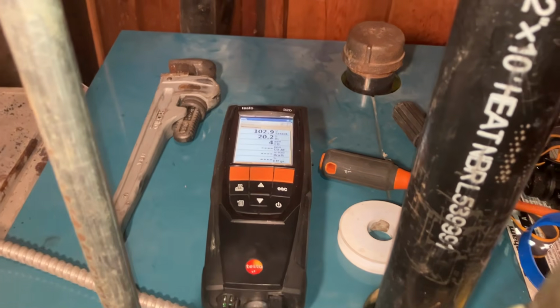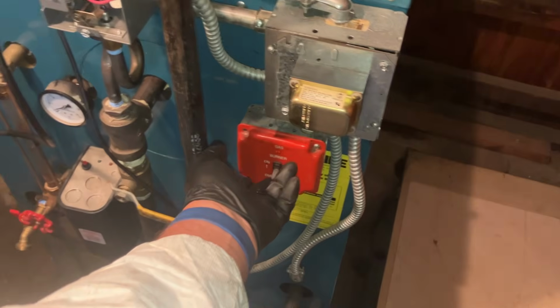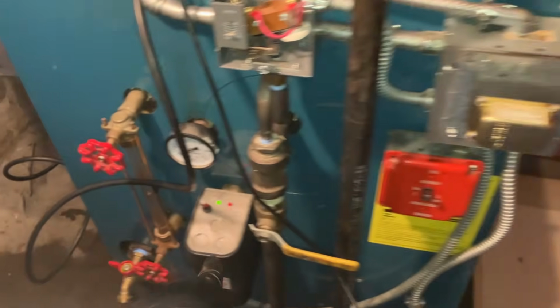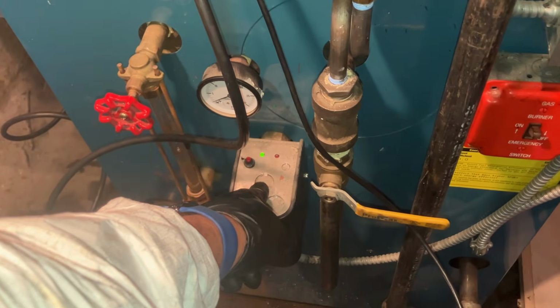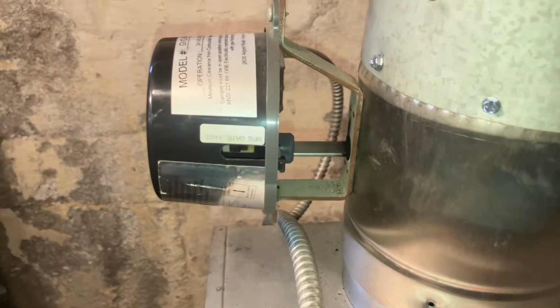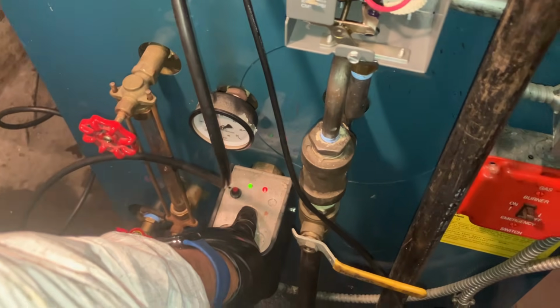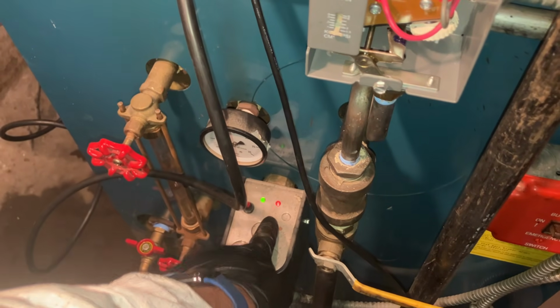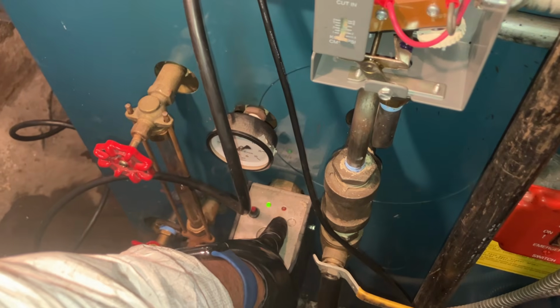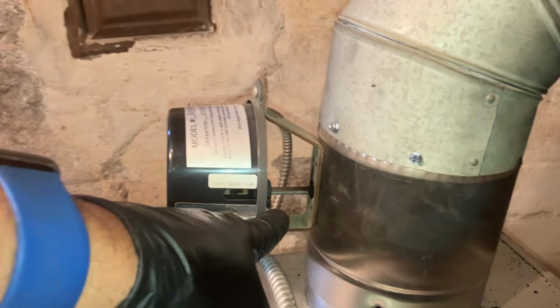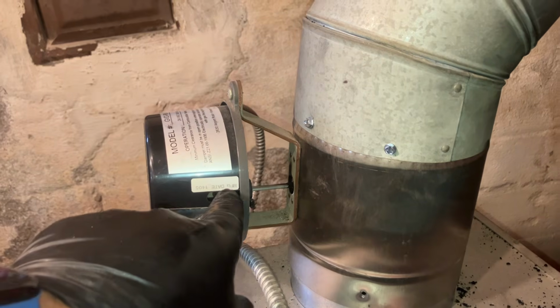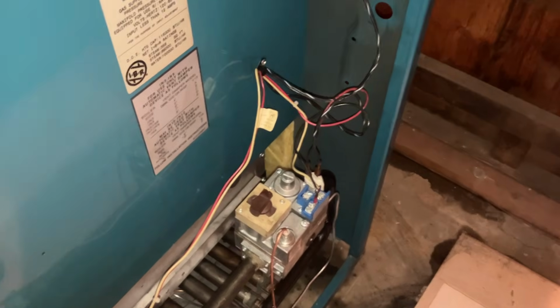Look at that, 103 degrees with nothing on. It's crazy. Ready? Okay, thermostat relay is energized. Our low water cutoff is doing its cycling on procedure. Automatic vent damper, if it was open, it's going to close. Damper is closed. Once the low water cutoff finishes its startup process, that light will turn off. The damper will open. The end switch will close, and we'll get power to the gas valve.